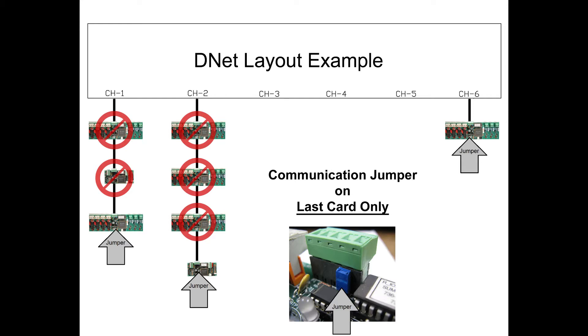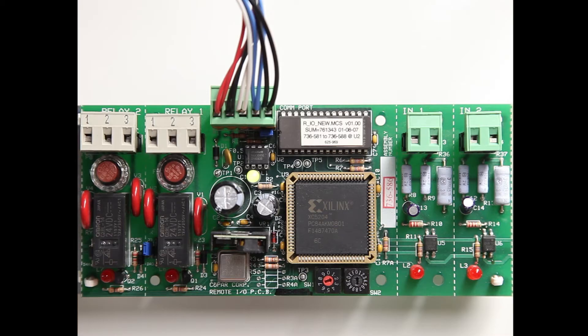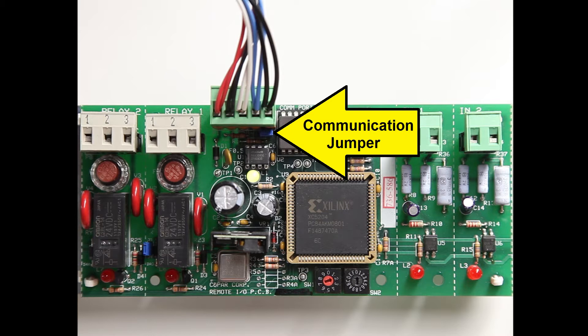If the jumper is not in the correct position, all cards on the string may not work correctly. This is an example of a DNET board. Here is the communication jumper, which we will be talking about in this video.